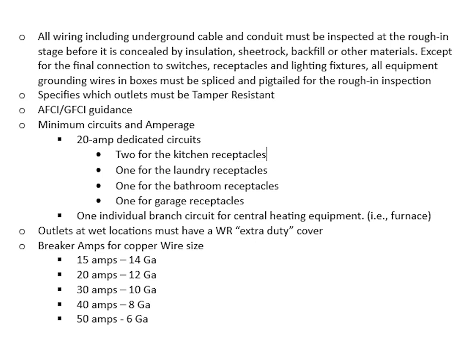It specifies which outlets must be tamper-resistant. It gives AFCI, GFCI guidance. More on these later. It specifies minimum circuits and amperage. 20 amp dedicated circuits, 2 for the kitchen receptacles, 1 for the laundry receptacle, 1 for the bathroom receptacles, 1 for the garage receptacles. There must also be 1 individual branch circuit for central heating equipment, i.e. your furnace. Outlets at wet locations must have a WR extra duty cover.